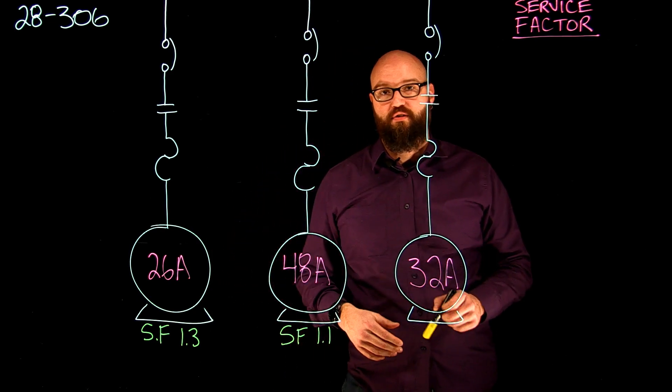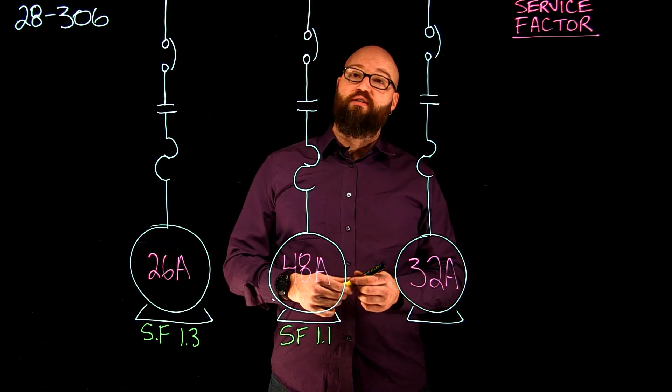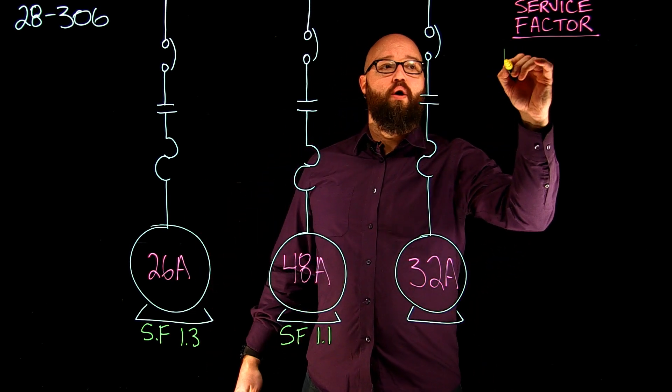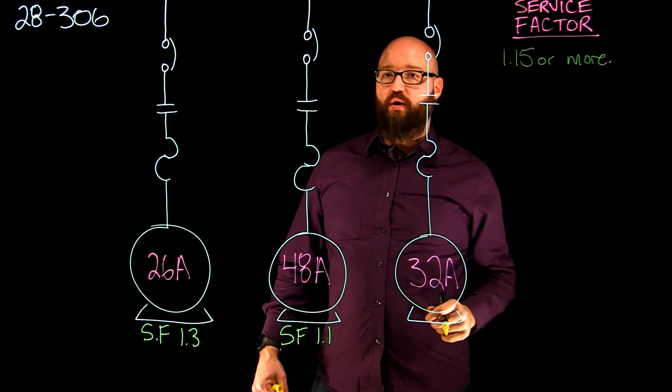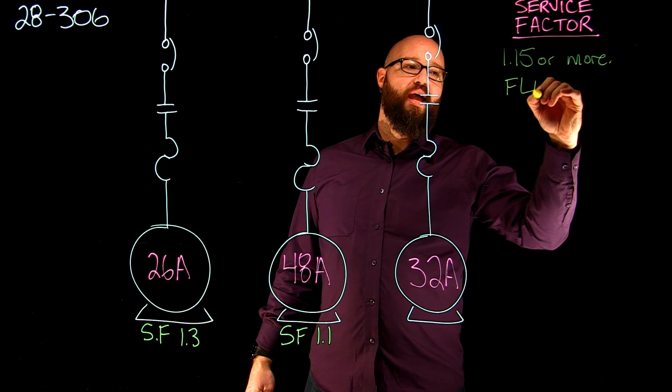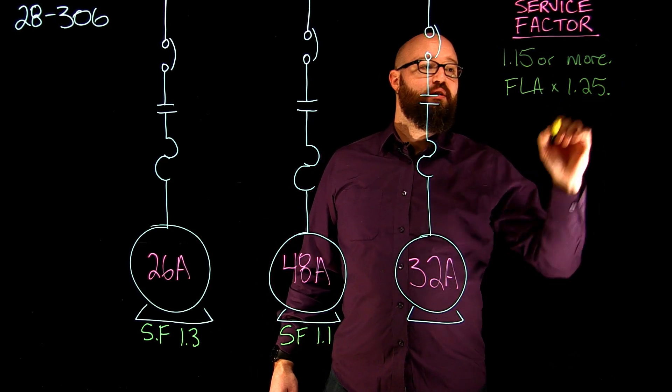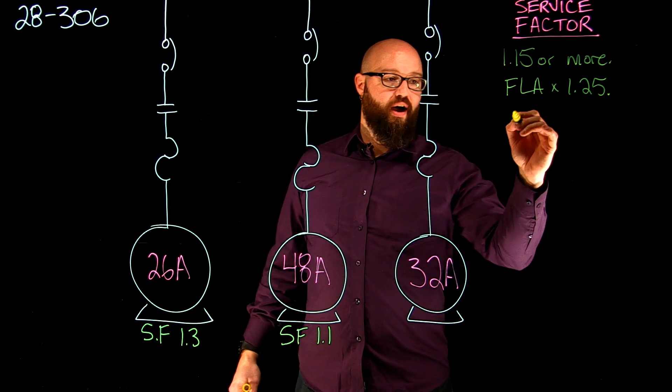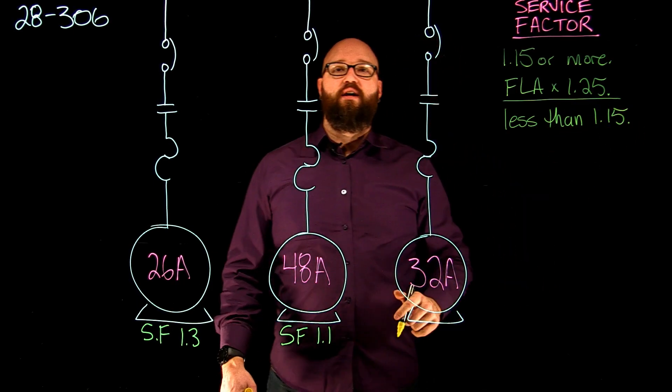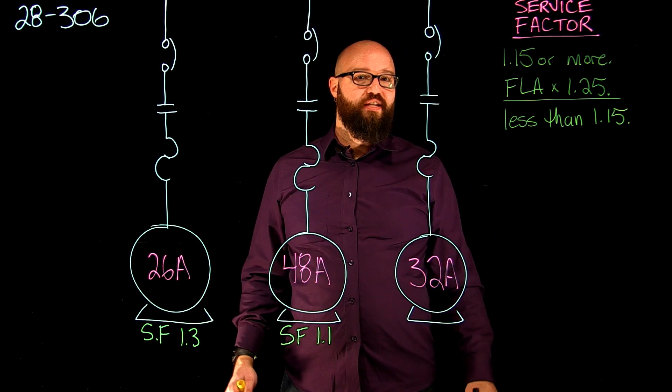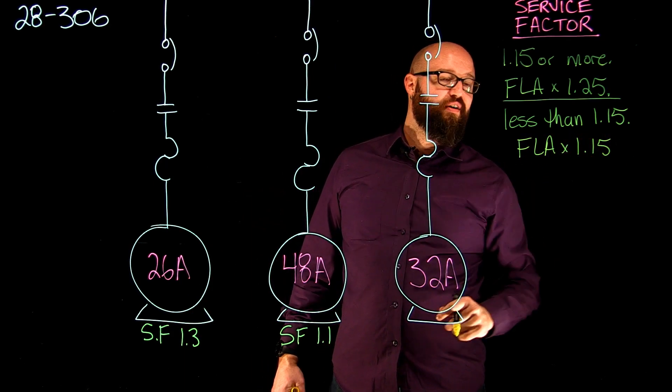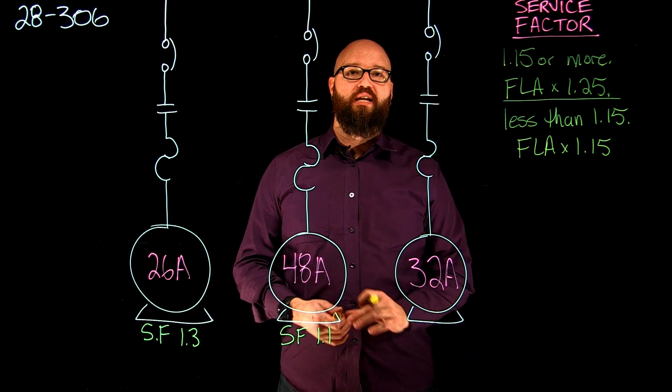If we take a look at 28306 in the 2015 Canadian Electrical Code, it tells us for marked service factors of 1.15 or more, we're going to multiply the FLA, or the full load current rating of the motor, by 125% or FLA times 1.25. If we have less than 1.15, we're going to take our FLA and multiply that by 115% or 1.15, and that would give us the maximum setting of overload device that I could have connected to that motor.